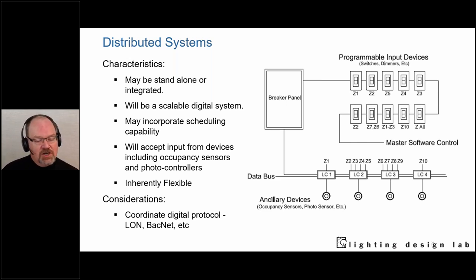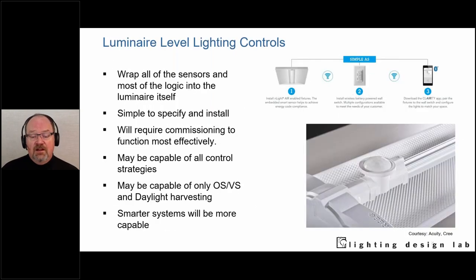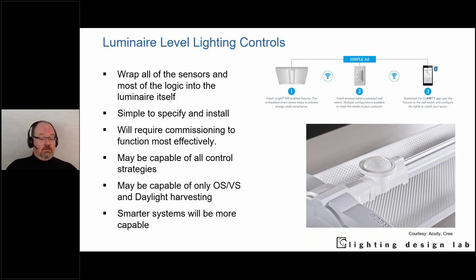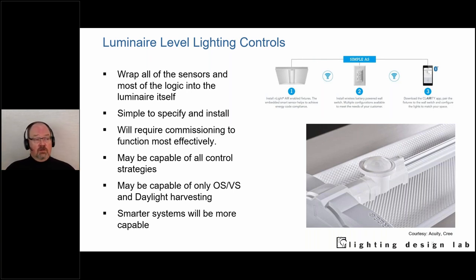The specialized approach we really like is luminaire-level lighting controls, or LLLC. You take all the devices — the load controller that tells the fixture to dim up, dim down, on, or off — and tie it in with a sensor on board the light fixture. That sensor has occupancy, vacancy, and daylight sensing already built into each individual light fixture. You just put them up in the ceiling — very simple to design, specify, and set up.